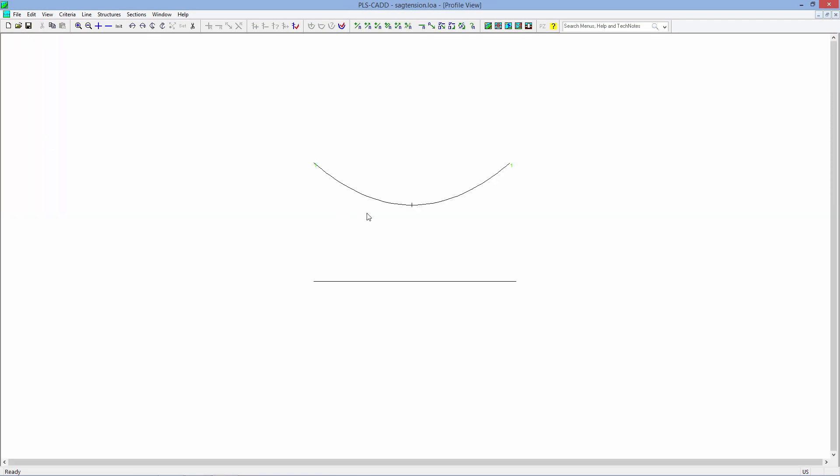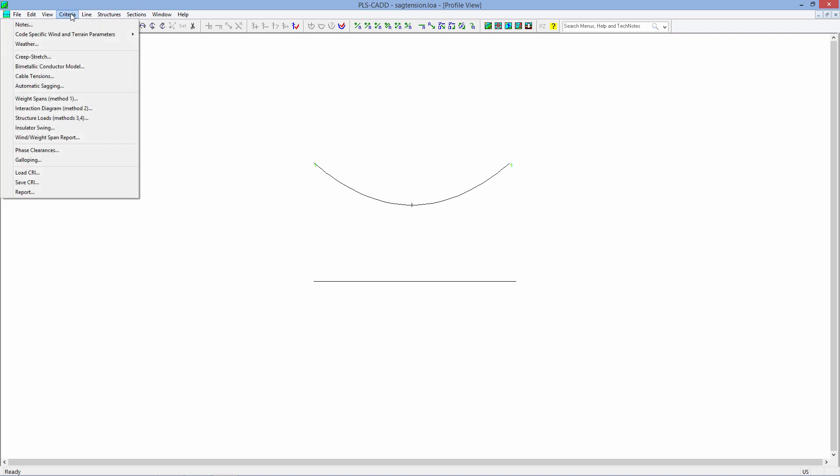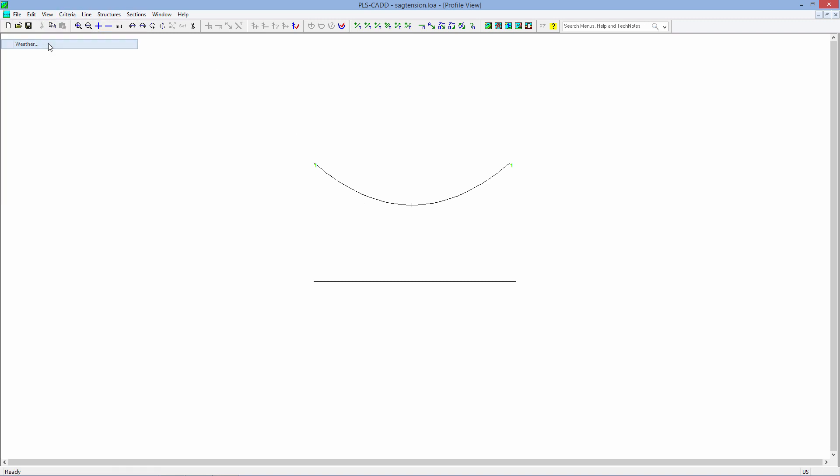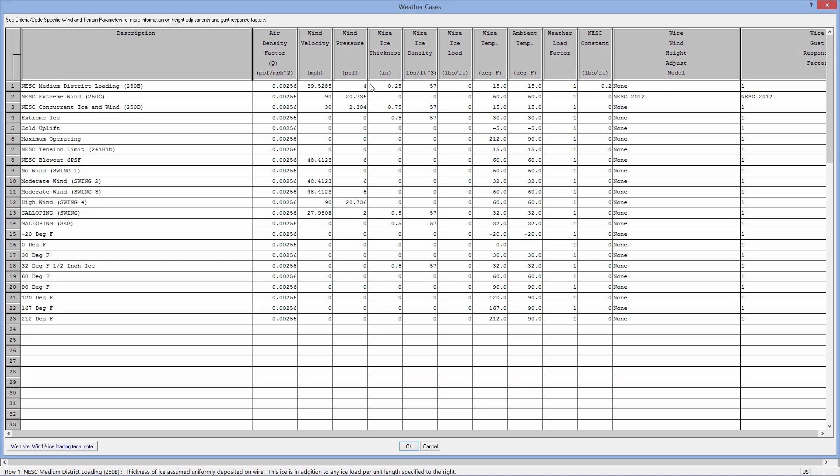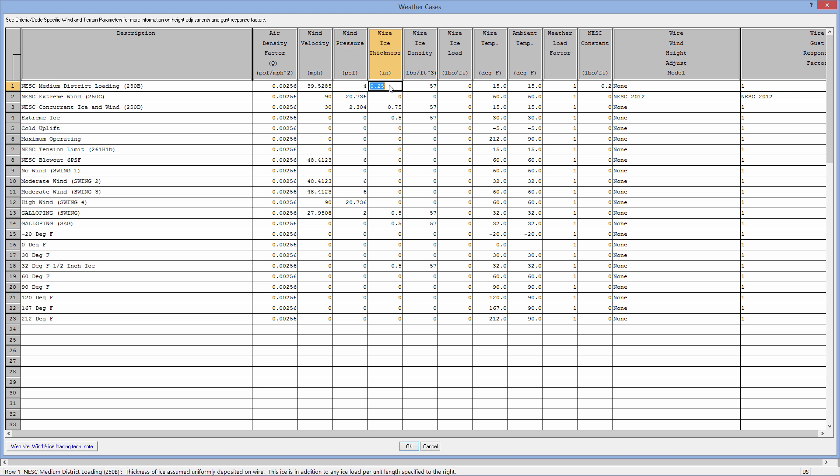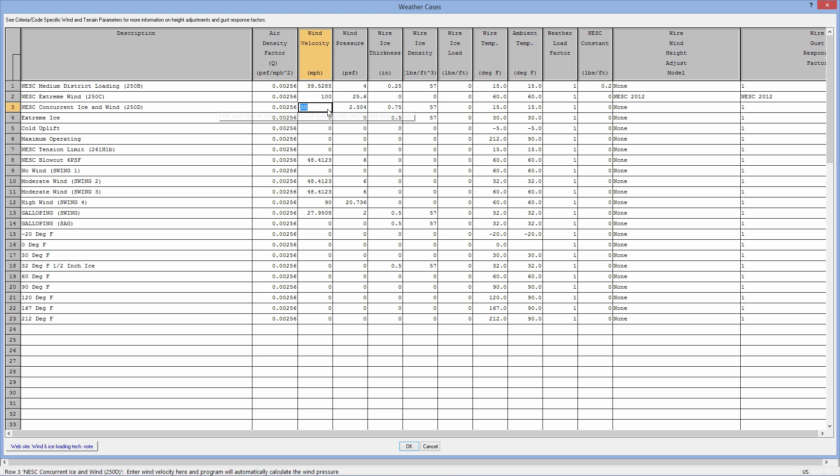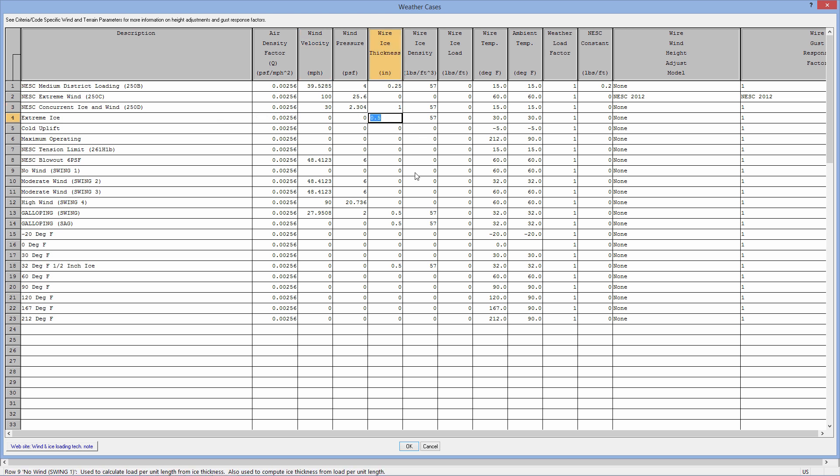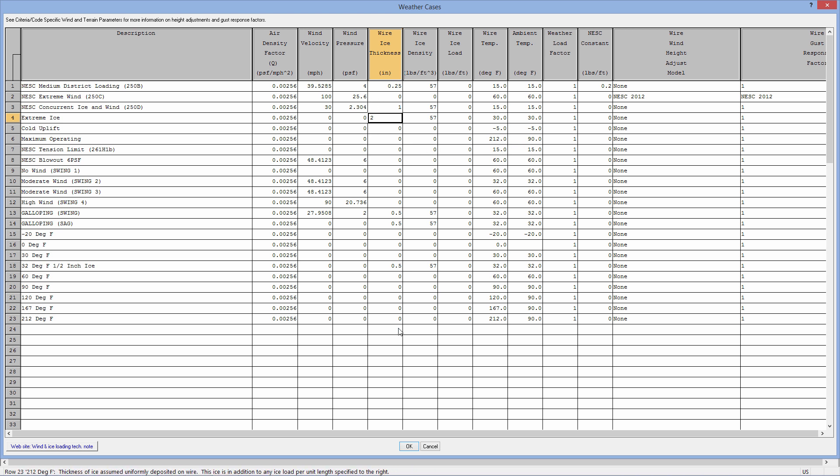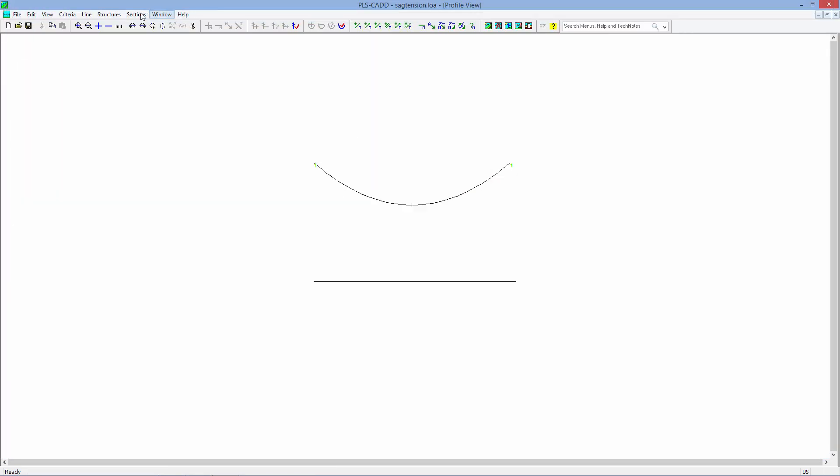Adjusting any things within PLS-CADD Lite are very easy. If you go to Criteria, Weather, if you want to change your wind speed, if you want to go from the NESC medium 4 pounds per square foot to another one, for example, if you want to use a different ice, if you want to use a different wind speed, for example, maybe you're in a 100-mile-per-hour wind speed district, or maybe you're in a 1-inch ice district for 250D. You'd also like to design this for an extra 2-inch ice. Very editable, whatever you want to do on your projects. You can just change the numbers here, click OK.